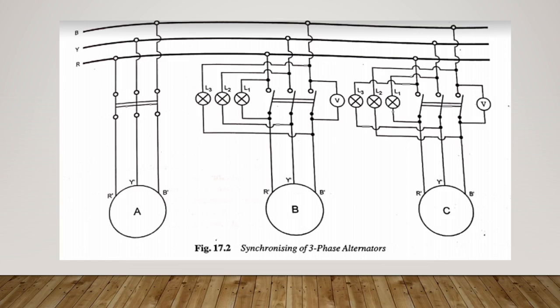If the incoming alternator B is properly connected, all the three lamps should become bright and dim together. If they brighten and dim in sequence, it shows that alternator B is not properly connected with the bus bars and the phase sequence of incoming alternator B is reversed relative to the system. To correct this, any two of the leads on either the alternator side or the line side of the switch will be interchanged. We can get the same effect by reversing the direction of rotation of the alternator. Once alternator B is properly phased out, it will always be correct unless either the wiring or the rotation is altered. So establishing a proper phase sequence is not a continual part of the synchronizing process of alternators.